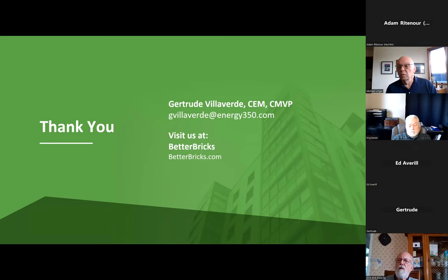Okay, so we're talking about return on investment. That's not something that I personally have looked at for these projects. We've looked at, like I said, the costs per square foot for installing these systems, but it really depends on the system. And I think what's important is what the baseline equipment is that we're comparing the VHE DOAS system to. Like there was that one project where they started off with that 610 heat pump ducted unit, and it seemed like the energy savings weren't as significant as other projects, but that's because they started with an efficient baseline to begin with. So it really depends on the building and how bad a baseline they've got. And so we focus more on the actual cost of installation.